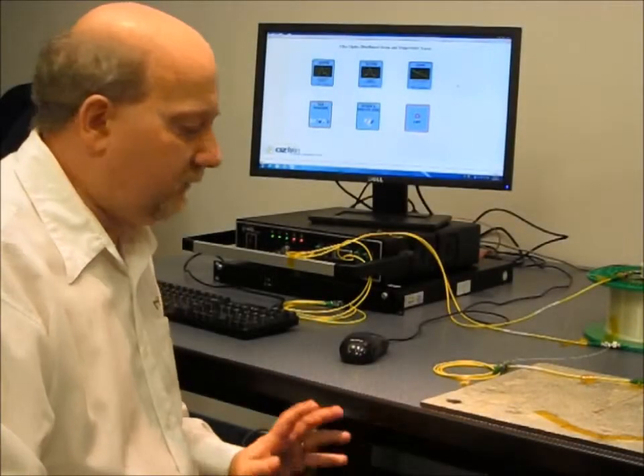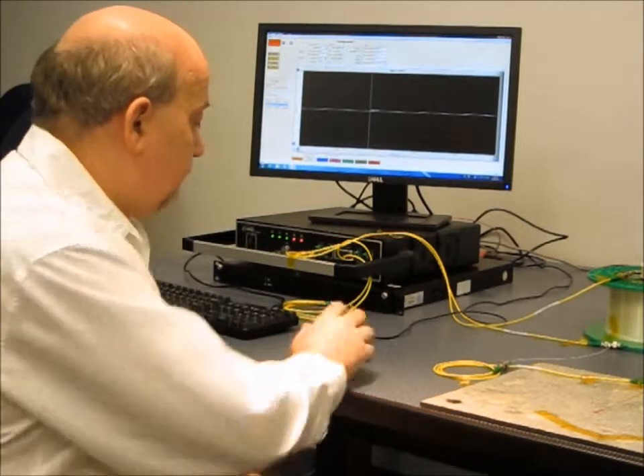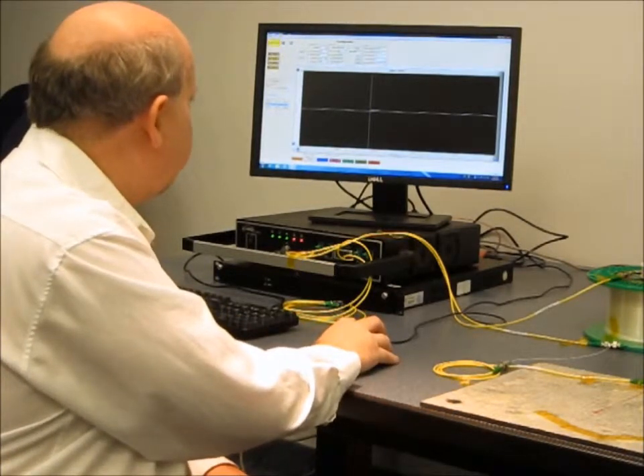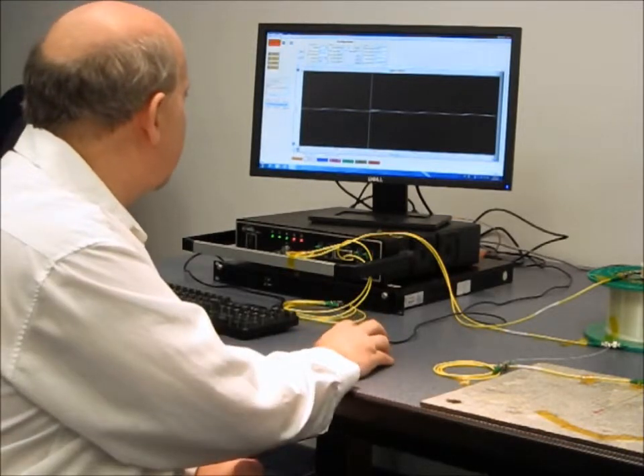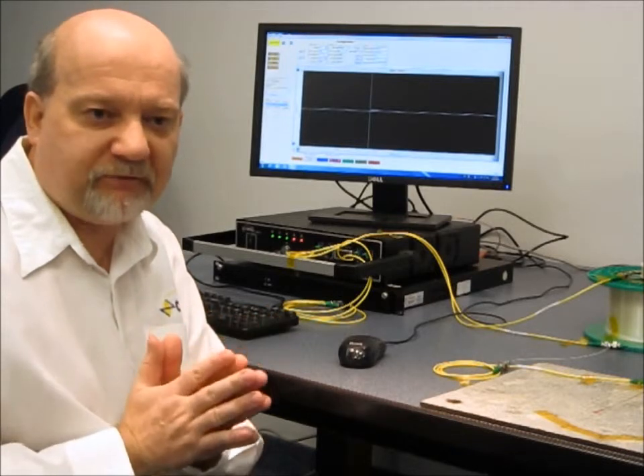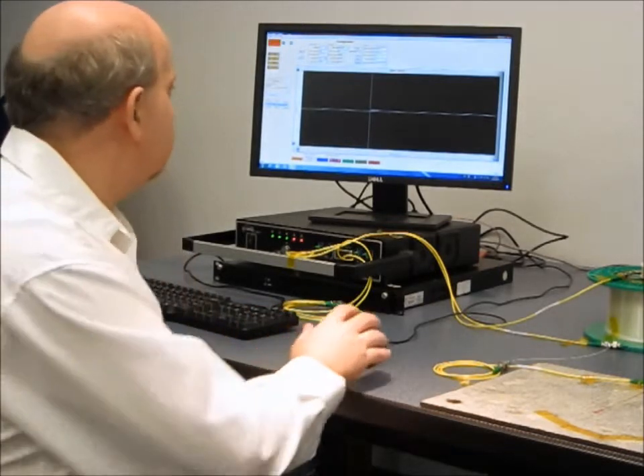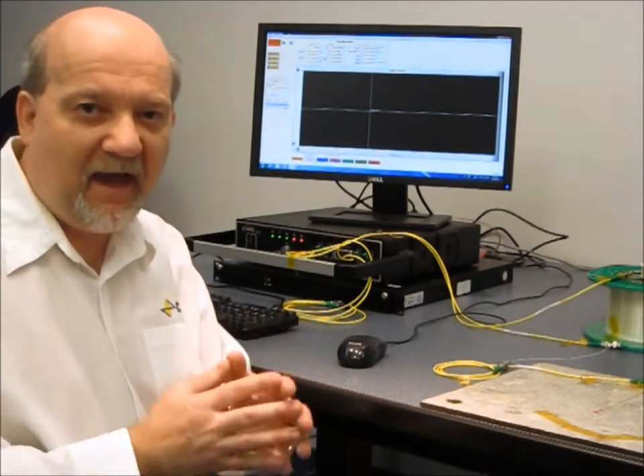Let's start the test. So let's set up the instrument to make our measurements. We are going to pick BOTDA for making the measurements. We've set the fiber length to be a thousand meters long, slightly longer than what our actual setup is. Notice, our pulse width is set up as one nanosecond. With one nanosecond pulse, the spatial resolution from our pulse is ten centimeters.